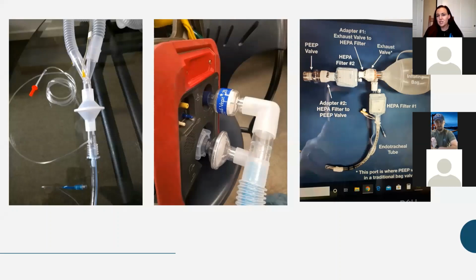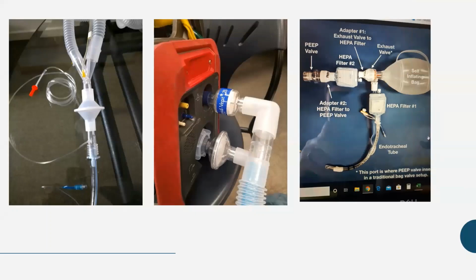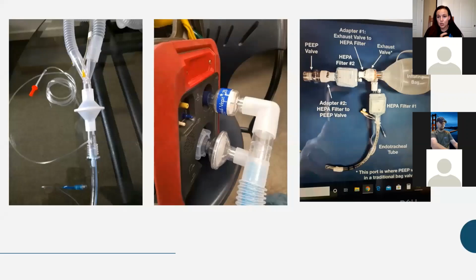And then the picture with just the ET tube and the BVM, there are 2 filters on there. That is not necessary, especially if you're trying to conserve filters. You can either put one right at the ET tube or on the exhalation side before that PEEP valve. In this setup, I think it might be easier to put it right at the ET tube just to make sure you're not messing with the efficacy of the PEEP valve and things like that.